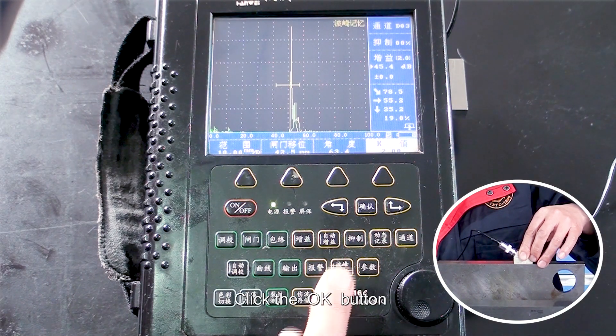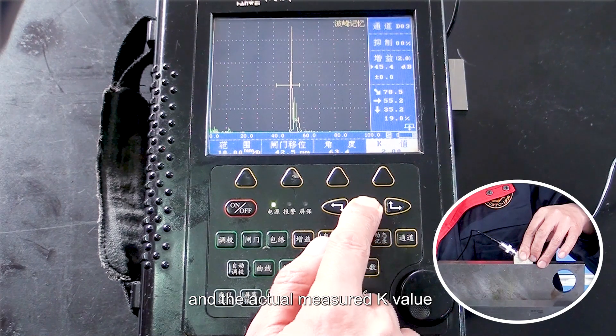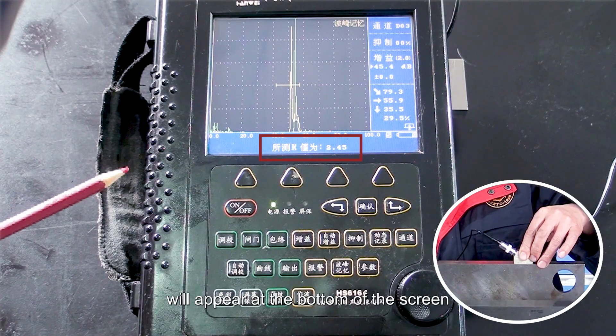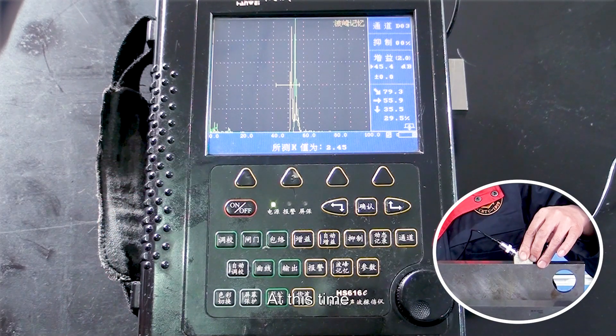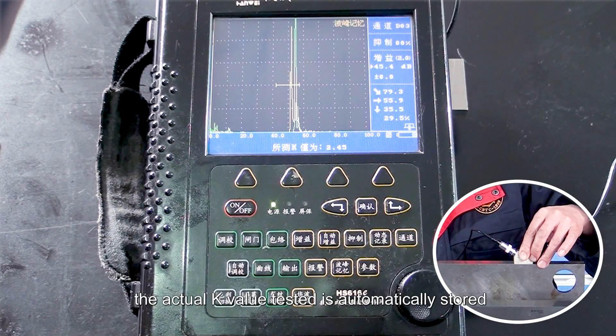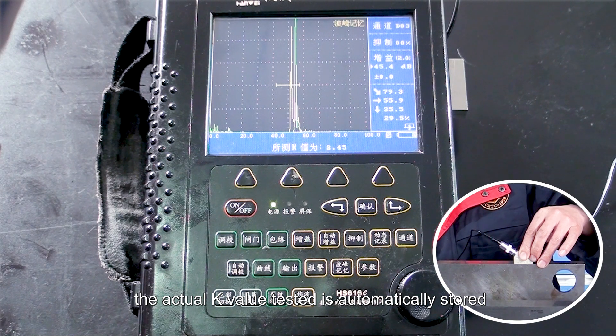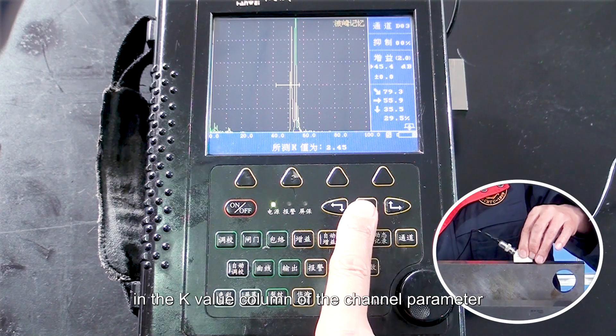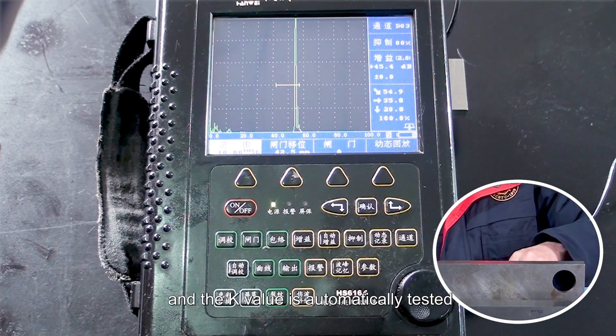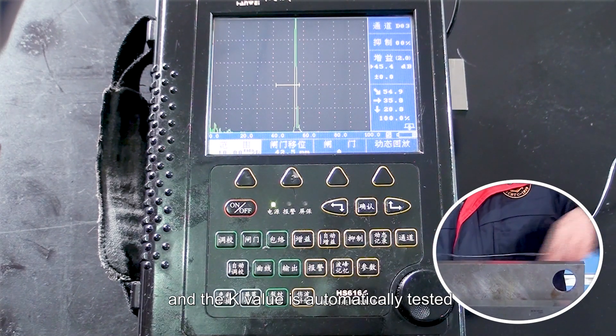Click the OK button, and the actual measured K-value will appear at the bottom of the screen. At this time, the actual K-value tested is automatically stored in the K-value column of the channel parameter, and the K-value is automatically tested.